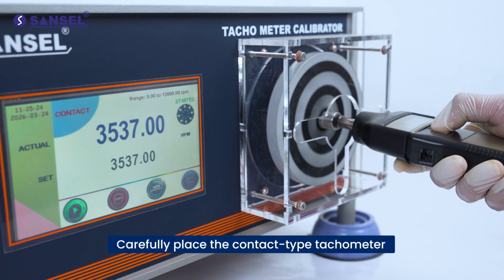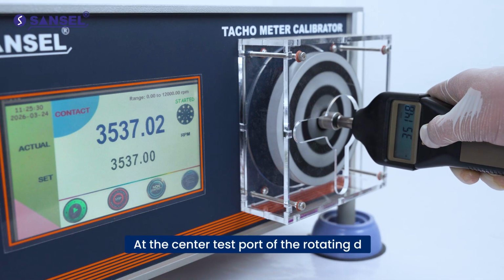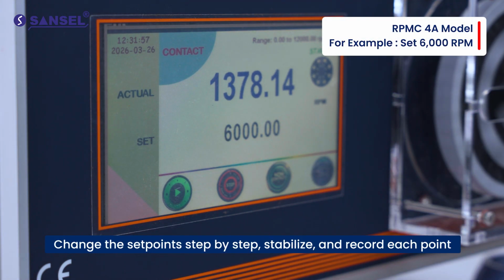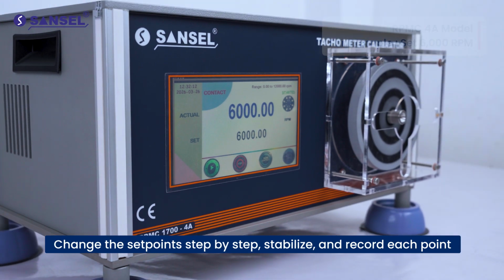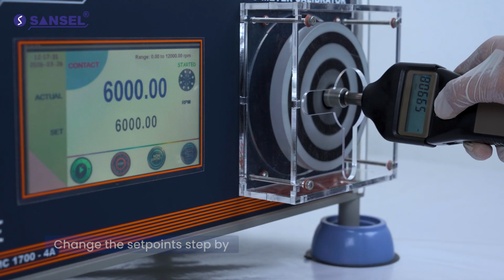Carefully place the contact type tachometer at the center test port of the rotating disc. Hold it steady without movement and verify the readings. Change the set points step by step, stabilize, and record each point.